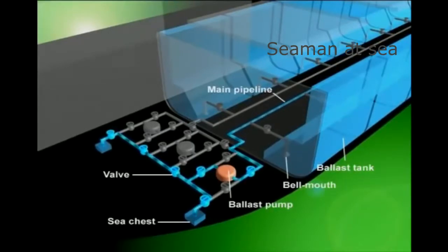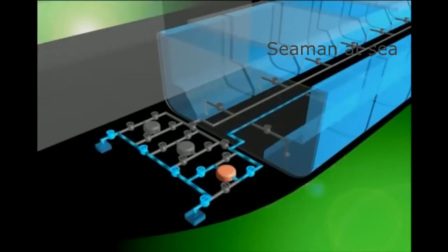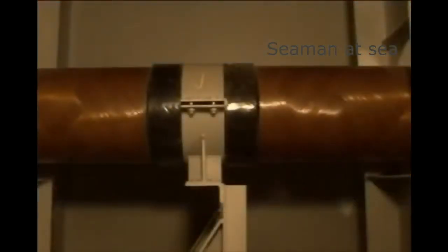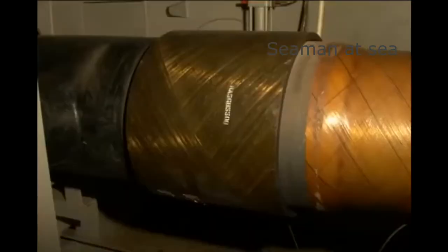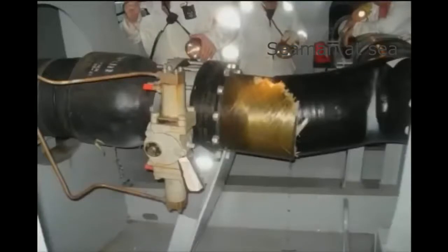Please note that improper handling of pumps and/or valves may result in various accidents. Shown here is a pipeline laid on the ship's bottom through which seawater flows for ballast filling or discharging. Joints that connect the pipes are called dressers. There are cases where dressers are damaged. This is an example of a water leakage accident due to dresser breakage caused by abrupt valve operation.